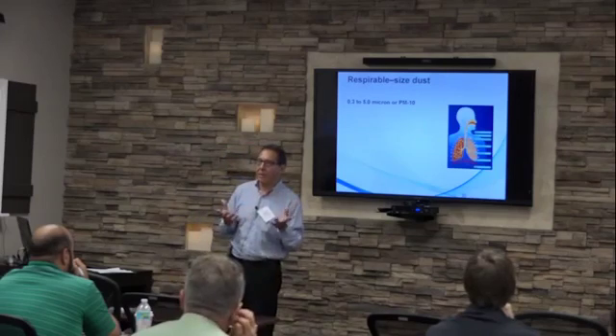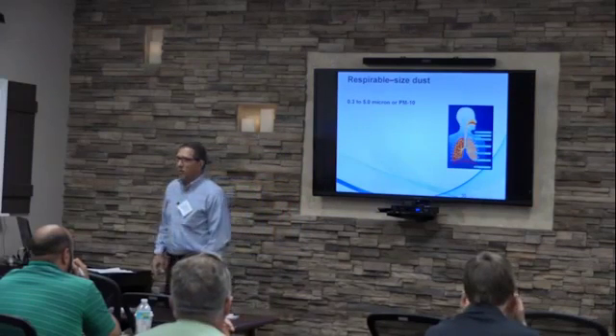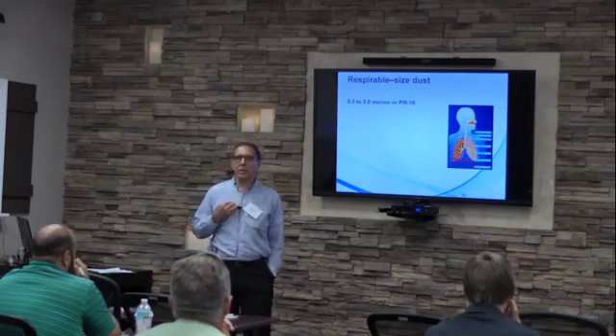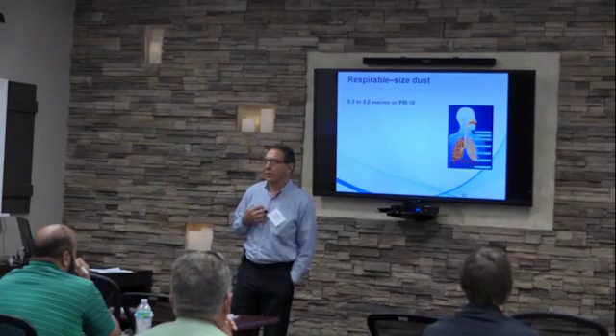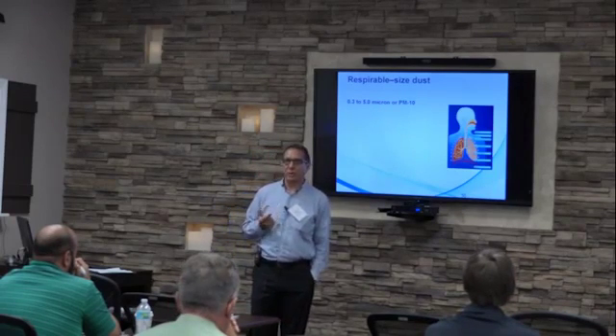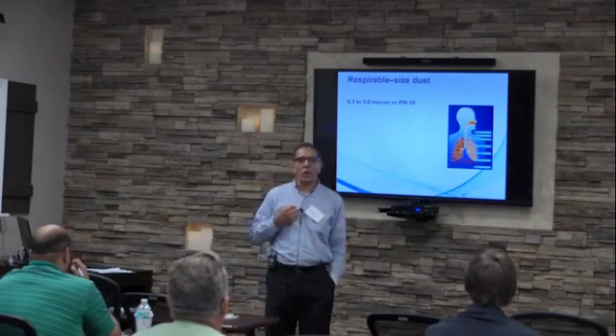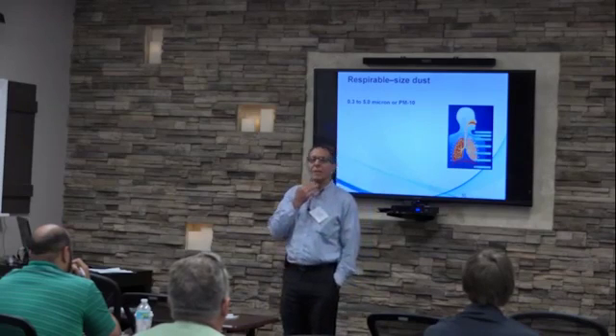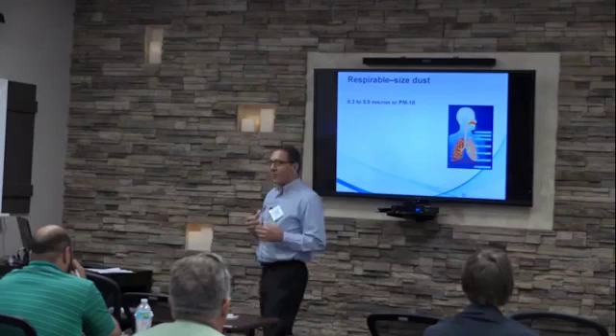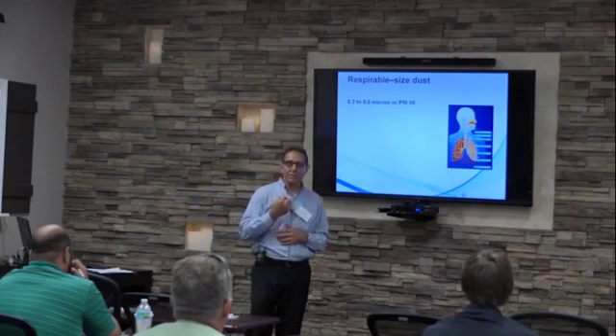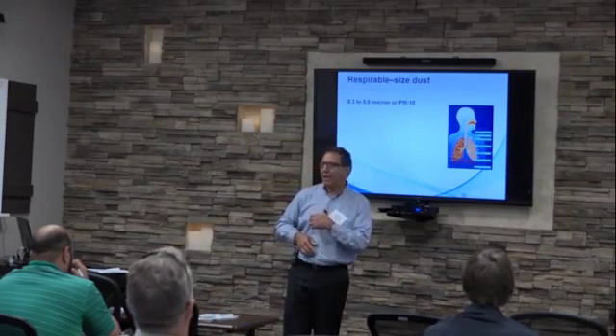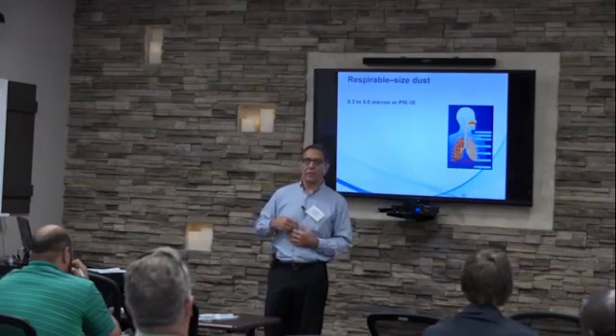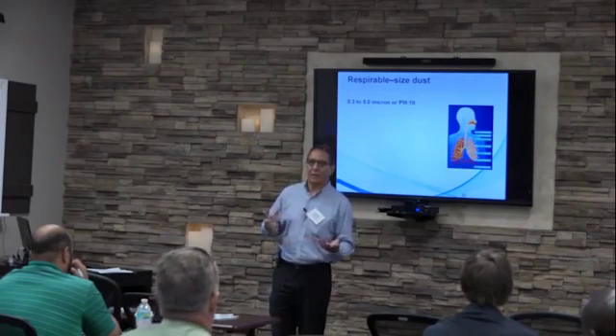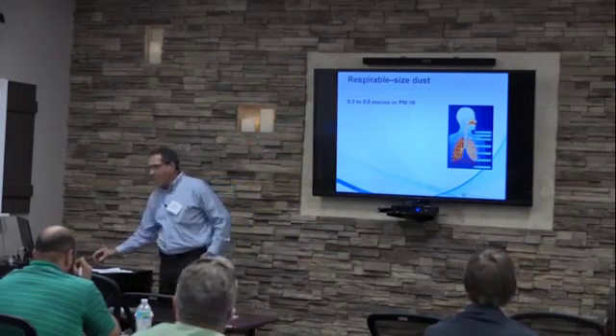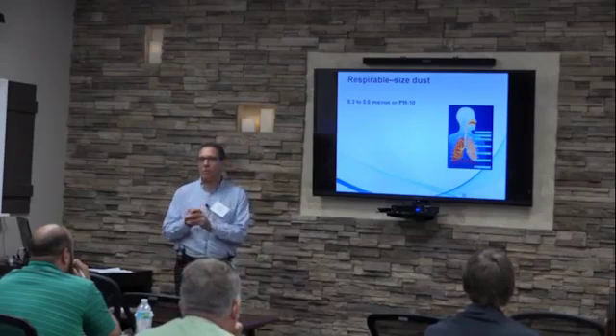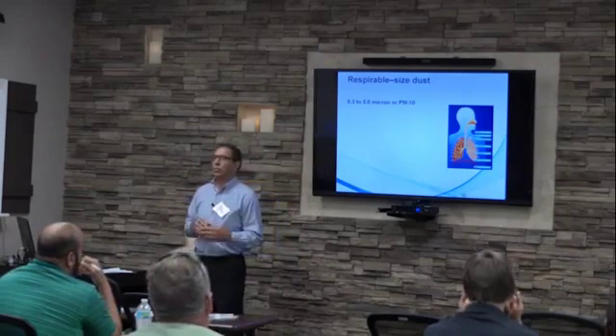Other things that we measure is respirable sized dust. Respirable sized dust is very fine dust that is typically present in every environment. Why respirable sized dust? Because it's so fine that it can enter the alveolar region of the human lungs and begin to cause infections and respiratory problems. Larger particles are not going to go all the way down into your lower respiratory system. They're trapped in your throat, on your mucous membranes, where we have protection. We have cilia that keep moving this mucous membrane out and naturally cleanse the airways. But once it reaches the alveolar region of the human lungs, it's not very easy to get rid of these contaminants. So it's 0.3 to 5 microns, and it is measured using a handheld particle counter, similar to the ones used in clean rooms.